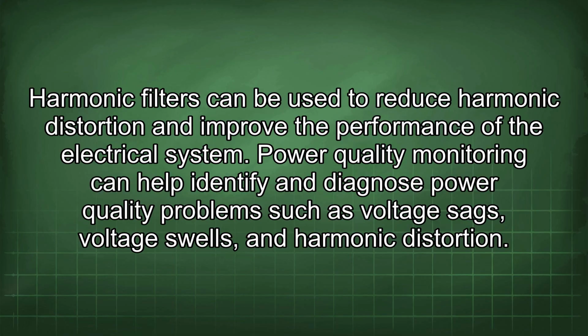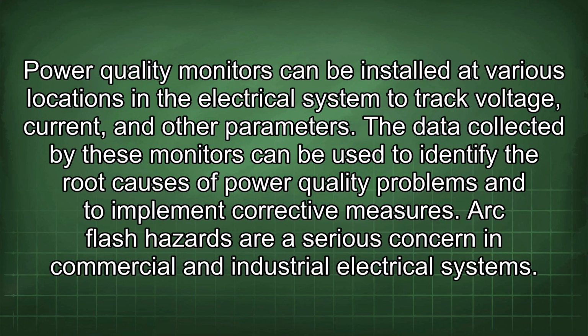Power quality monitoring can help identify and diagnose power quality problems such as voltage sags, voltage swells, and harmonic distortion. Power quality monitors can be installed at various locations in the electrical system to track voltage, current, and other parameters. The data collected by these monitors can be used to identify the root causes of power quality problems and to implement corrective measures. Arc flash hazards are a serious concern in commercial and industrial electrical systems.